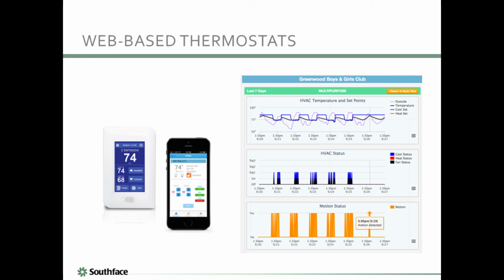This issue is not unique to recreation centers. Nearly all small commercial buildings have thermostat schedules that are not optimized for maximum efficiency. Wired thermostats in small commercial buildings are usually set to hold instead of running a program. Programmable thermostats often have unintuitive interfaces for adjusting temperature set points and schedules. To make matters worse, most buildings have multiple different types of programmable thermostats, each with its own interface.